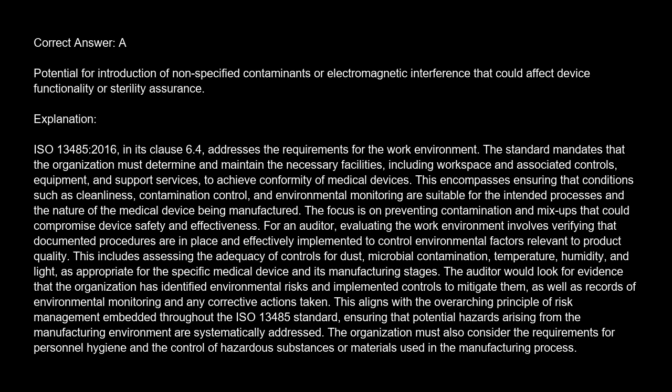Explanation: ISO 13485-2016, in its Clause 6.4, addresses the requirements for the work environment. The standard mandates that the organization must determine and maintain the necessary facilities, including workspace and associated controls, equipment and support services, to achieve conformity of medical devices. This encompasses ensuring that conditions such as cleanliness, contamination control, and environmental monitoring are suitable for the intended processes and the nature of the medical device being manufactured. The focus is on preventing contamination and mix-ups that could compromise device safety and effectiveness.